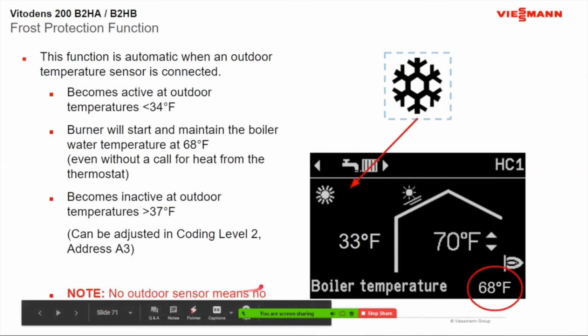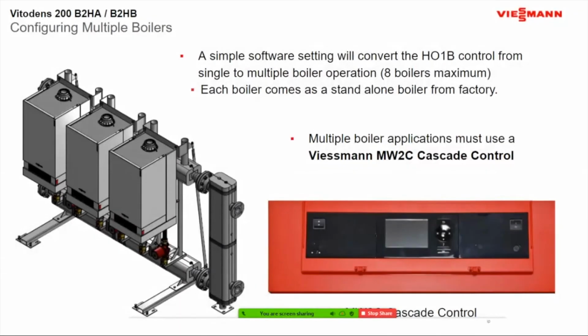No outdoor sensor means no frost protection, no boiler protection, no outdoor shut off, cold weather shutdown. So this is the MW2C. This is your cascade control for the multiple boiler setup. We sell a rack system with 3 or 2 boiler setups. And like I said, you could have up to 8 boilers on a rack system. This cascade control will control all 8 boilers.